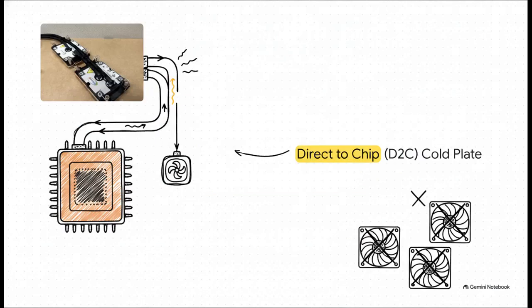So how do we actually apply this in a real server? Enter direct-to-chip, or D2C technology. Instead of a massive, super loud fan sitting on top of your processor, you have a sleek, contained cold plate sitting directly on the running chip. There's a thermal transfer material right between the silicon and this copper plate.